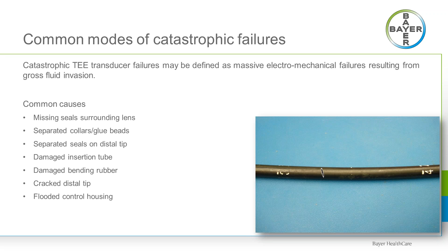One thing to think about is these failures can also provide a means of harboring bacteria and could be a potential source for cross-contamination. Disinfecting a probe through immersion with a separated collar or a damaged distal tip is really another root cause of gross fluid invasion. So although not as common, a cut or a damaged insertion tube can be another source of gross fluid invasion. By far, the bending rubber is the component that is most likely to fail, resulting in gross fluid invasion.